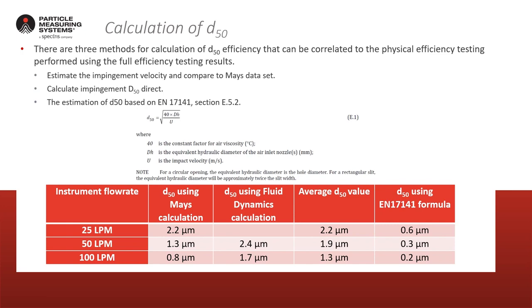For calculating the D50, there are three methods. The first is estimating the impingement velocity and comparing to a chart that Mays developed — available in the technical white paper. The second is actually calculating the fluid dynamics to determine what size would impact at a given inlet velocity. The third is that EN 17141 also gives its own approximation formula for calculating a D50, with the formula shown on screen.